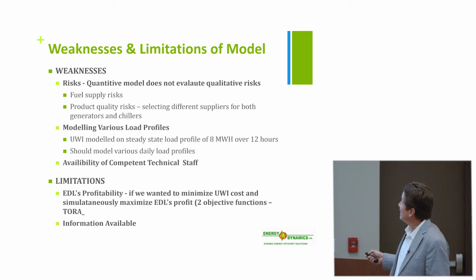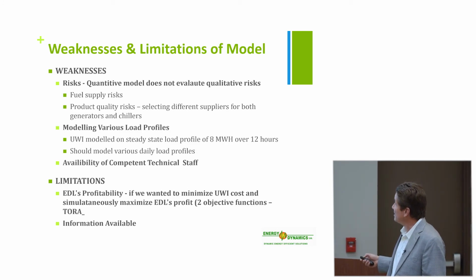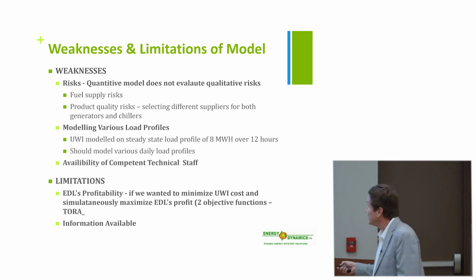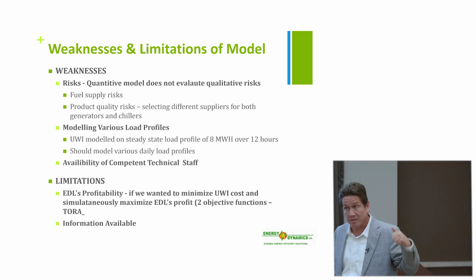Quantitative model does not evaluate qualitative risk - fuel supply risk, product quality risk, right? Selecting different suppliers for both generators and chillers. Modeling various load profiles - the model assumed a steady state load of 8 megawatts over 12 hours; it should model varying daily load profiles. Also, availability of competent technical staff.